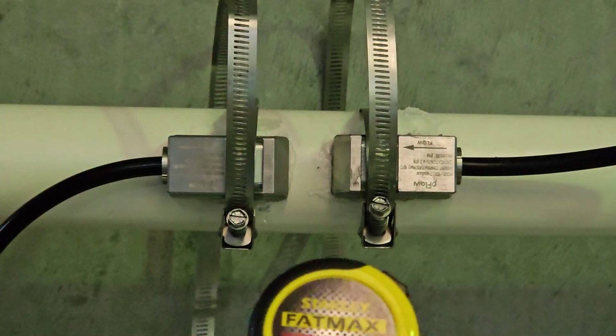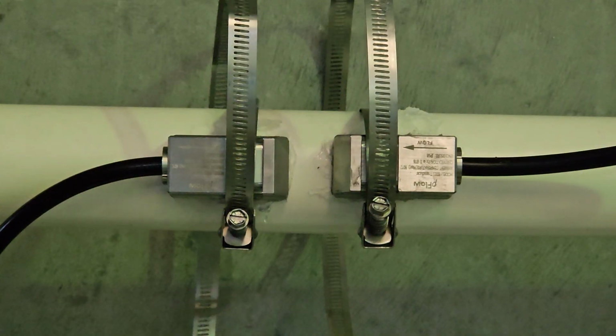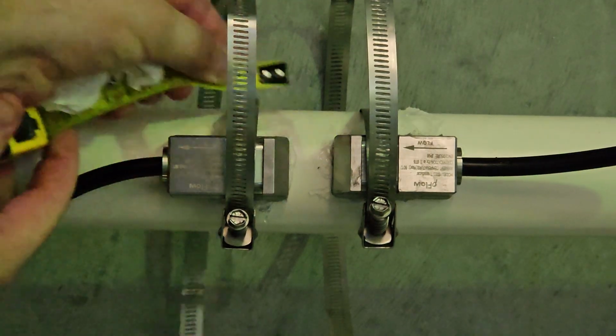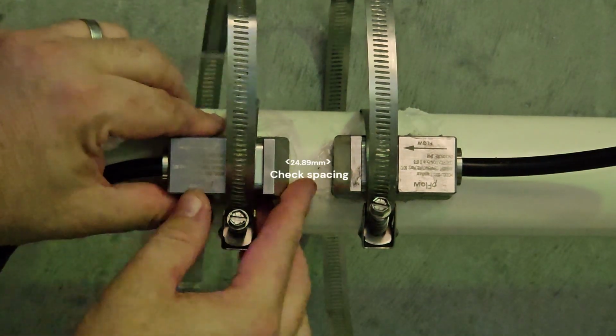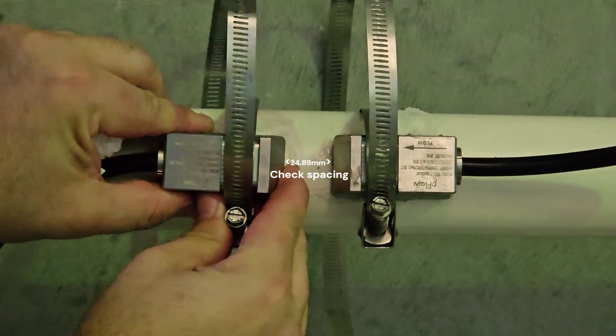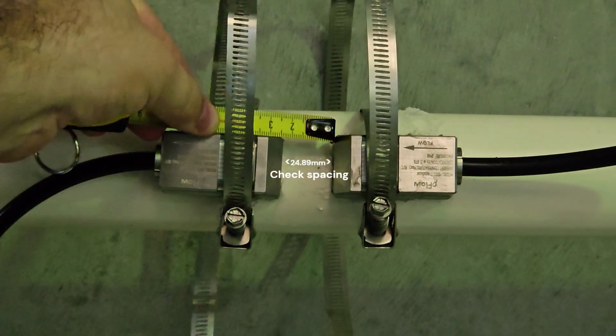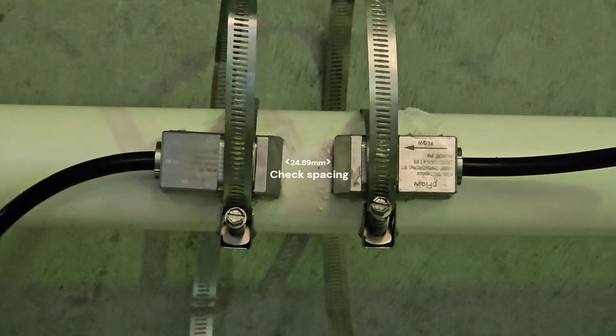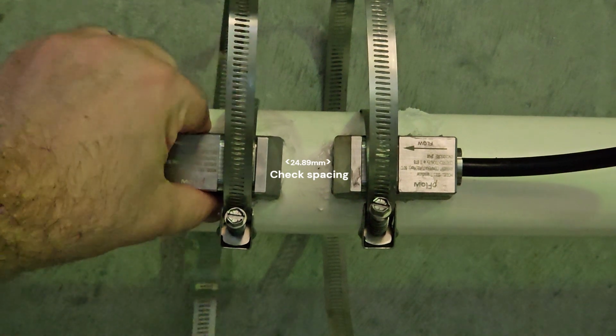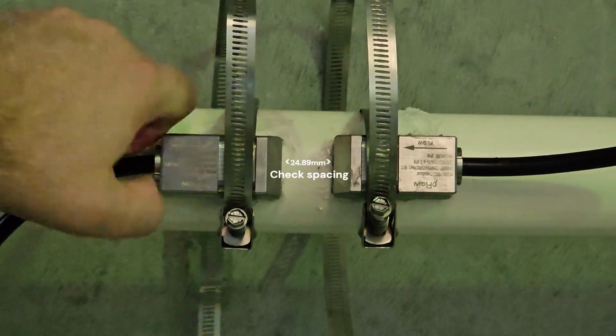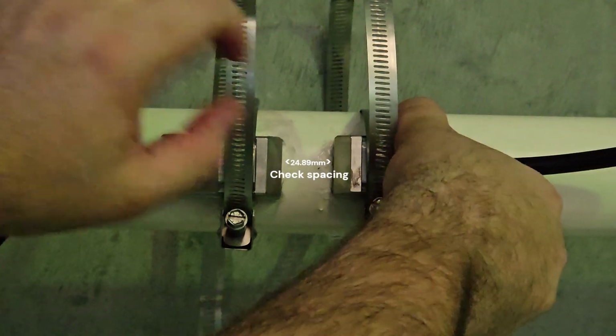Using a tape measure, I can make sure the sensors are accurately spaced, matching the required spacing which the meter had displayed. Make fine adjustments until properly spaced and tight. Ensure the sensors are aligned straight along the pipe. Double-check the spacing is correct, matching your meter, not the 24.89 mm of this example.